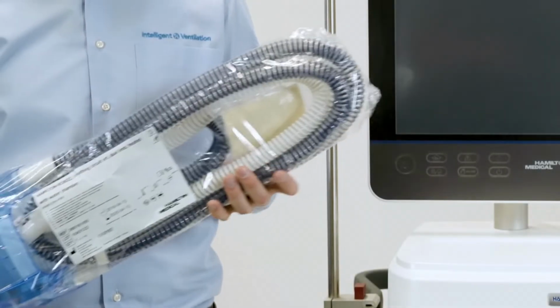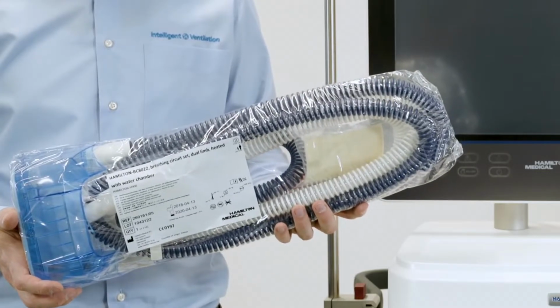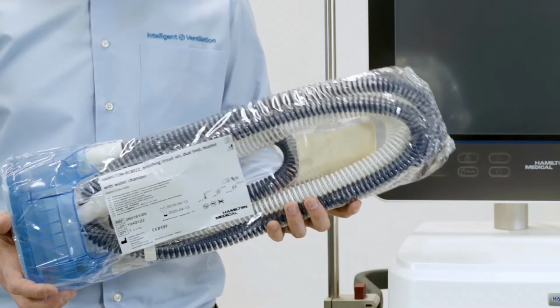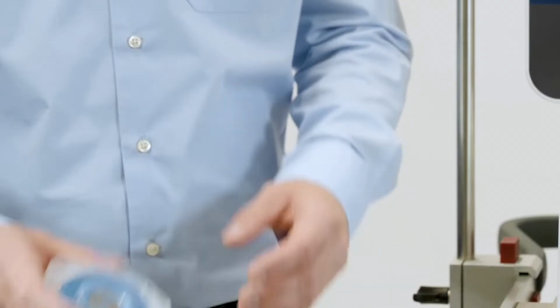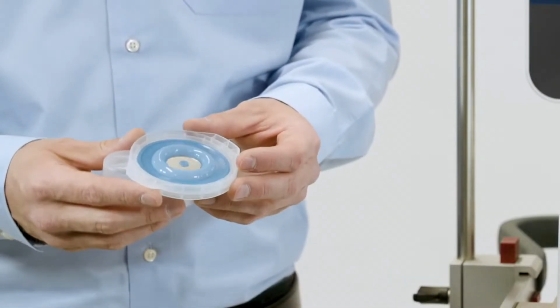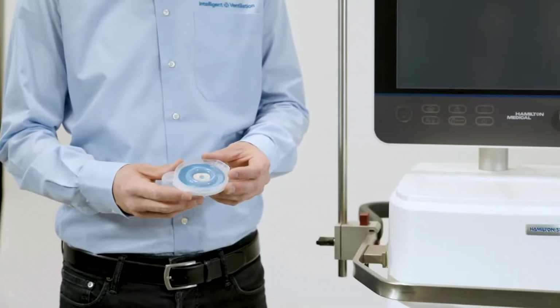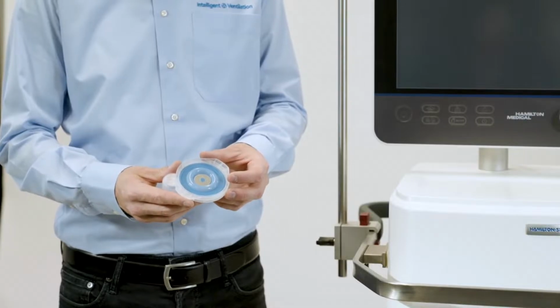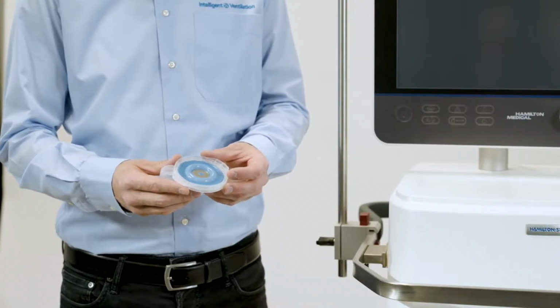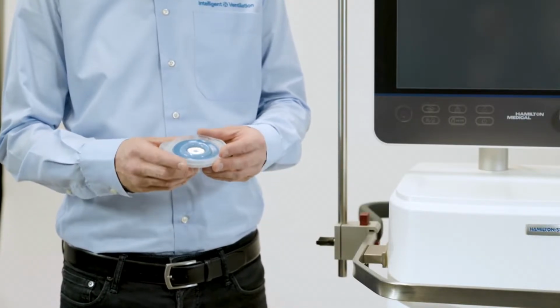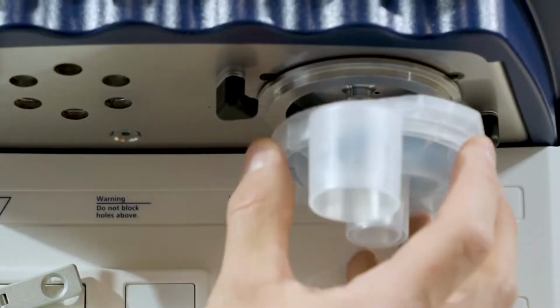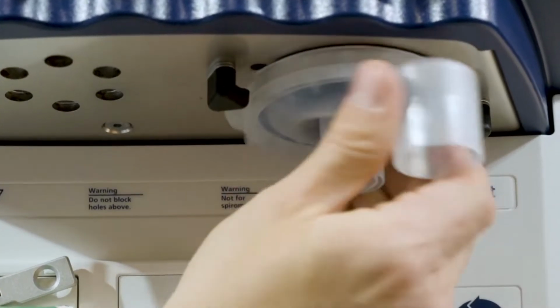If you plan on using a double-limb heated breathing circuit, start by installing the expiratory valve set. The expiratory valve set is delivered clean and ready for use. Always check the set before using it on the patient. Position the expiratory valve set in the expiratory port and twist it clockwise until it locks into place.